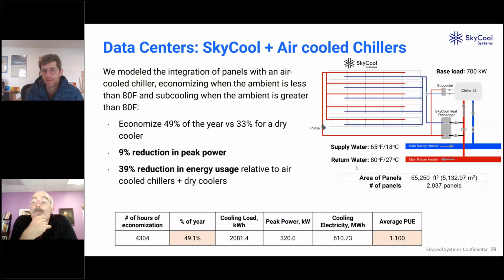Yeah. Does the system work with ammonia systems present in large refrigerated warehouses? Yeah, so we're actually today working on our first ammonia system. It's in Idaho. It's a potato cold storage facility, but it's ammonia, and it has an evaporative condenser. We're going to be using the same construct, pre-cooling and subcooling the system. So it's subcooling in the cooler times, pre-cooling in the warmer times.